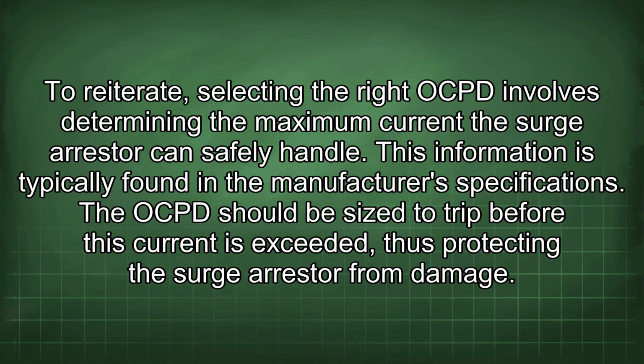To reiterate, selecting the right OCPD involves determining the maximum current the surge arrestor can safely handle. This information is typically found in the manufacturer's specifications. The OCPD should be sized to trip before this current is exceeded, thus protecting the surge arrestor from damage.